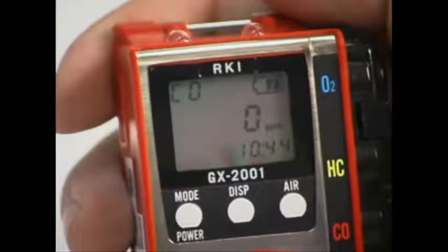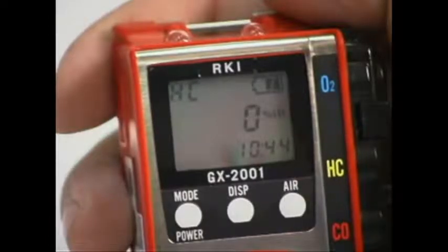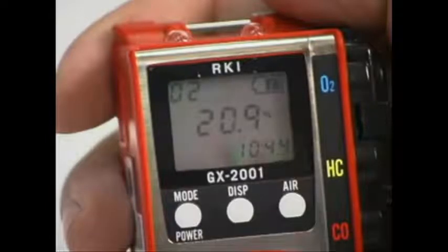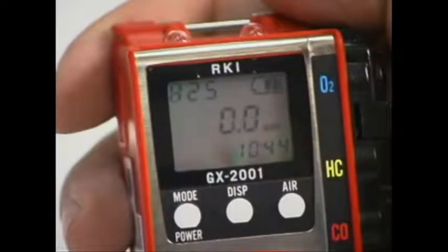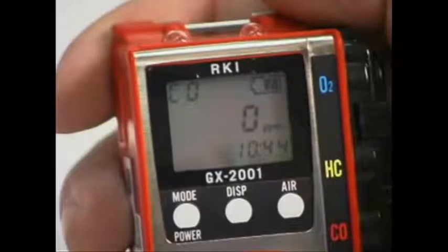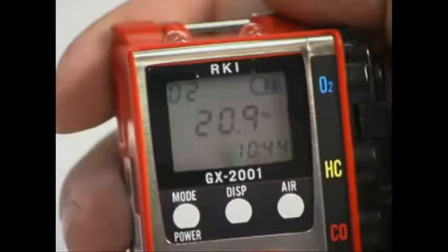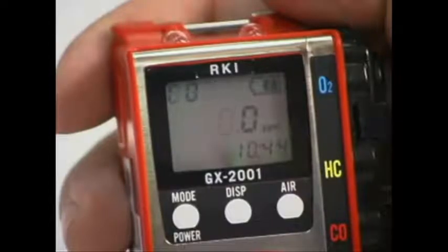The second consideration to keep in mind is that concentrations of a combustible gas of more than 100% LEL can affect the zero level or calibration of the combustible sensor if the concentration is high enough. Do not expose the combustible sensor to high concentrations of combustible gas, such as that from a butane lighter. Exposure to high concentrations of combustible gas may adversely affect the performance of the sensor.